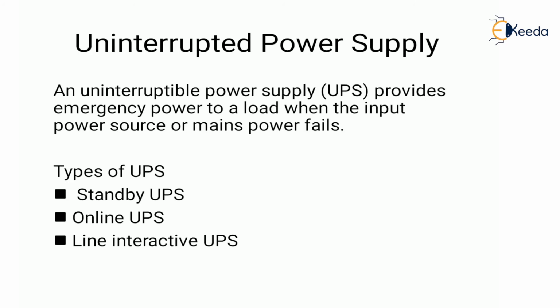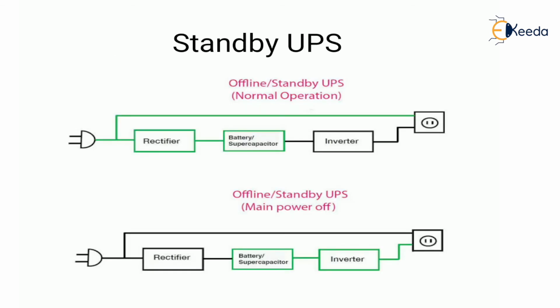First is the uninterrupted power supply, that is UPS. An uninterrupted power supply provides emergency power to the load when the input power source or mains power fails. Now, what are the types of UPS? First is the standby UPS, next is the online UPS, and the third one is the line interactive UPS. So, let's see the types of UPS one by one. First is the standby UPS. Offline UPS units are often referred to as standby systems, as the inverter, as you can see in the diagram, is in standby mode until the main power supply fails.